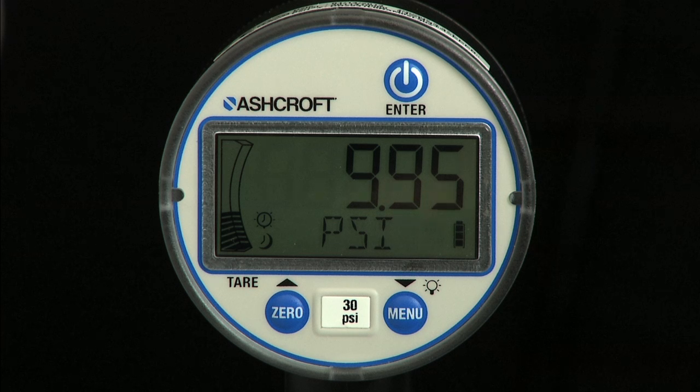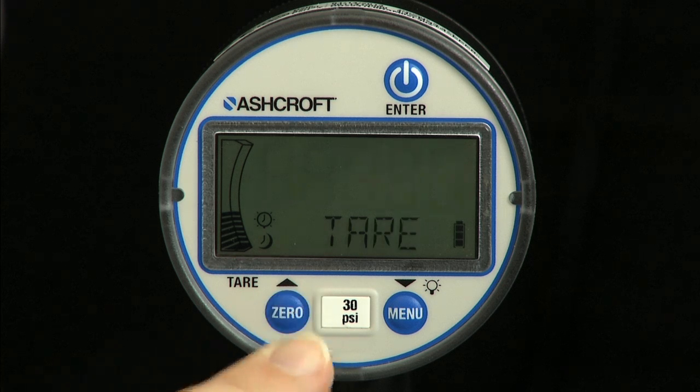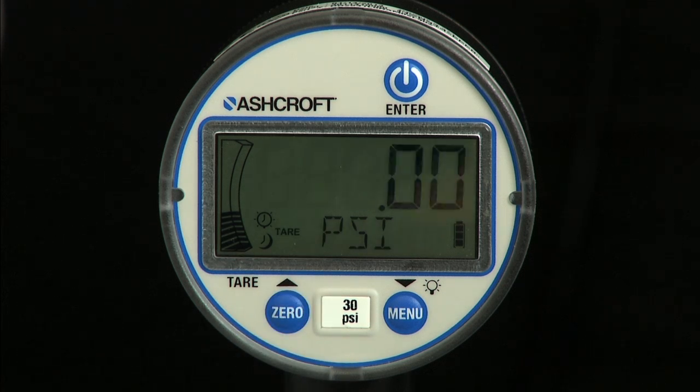The tare function is used to set the current pressure to zero temporarily. Tare is commonly used to measure a change in pressure during a specific task or event. When the gauge is in tare mode, the tare icon will be turned on and the numeric display will blink. To exit tare mode, use a short press of the tare key.